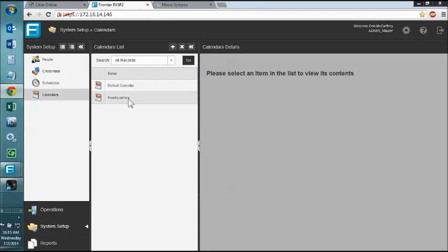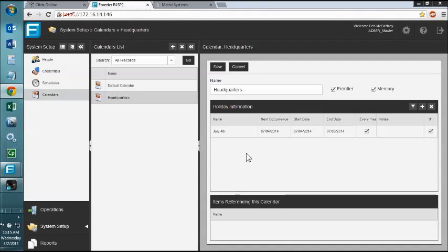All right, so here we go again. When we're talking about calendar items, you can bring up calendar items. You can create the calendar items, such as July 4th, Labor Day. You can create these here. It will immediately go back to the full application and start utilizing that. So wherever it sees a holiday that's July 4th, which is on Friday, then the application will know that it's looking for a special line or looking for that holiday line on the schedule. It'll be following that information versus its normal day, which would be a Friday. So you can set those calendar items up in the web client.